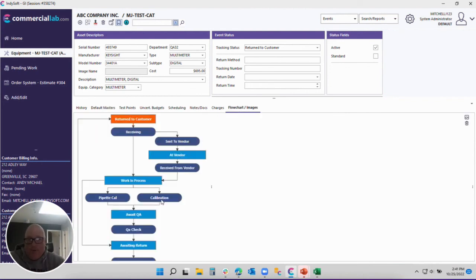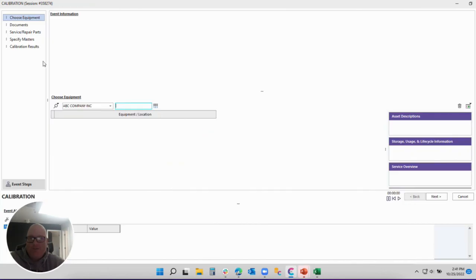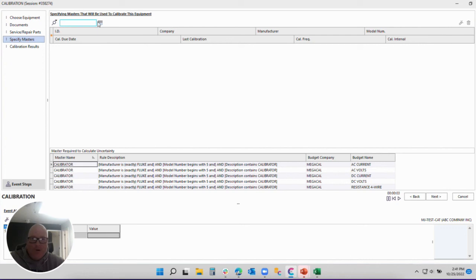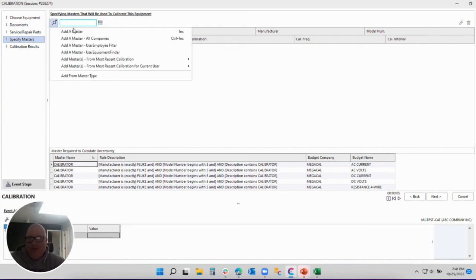As we're calibrating tools, just as a recap, I'll show you these 5 or 6 different options again. We all know that you have the ability to scan a barcode or type in the ID number, but you have the ability to look at all masters that belong to the facility or the company under test. You can also look across your whole database, maybe a shorter list of just employees. Of course, we give you Equipment Finder where you can build your own queries.